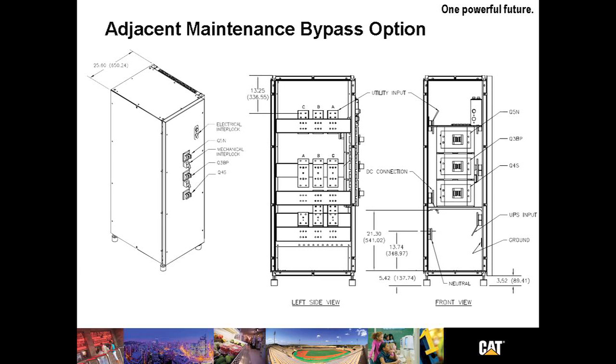The adjacent maintenance bypass option provides a three circuit breaker option for external wraparound and bypass for the system. Electronic interlocks are used in combination with Kirk keys. The matching cabinet is 26 inches wide. A remote version of this is available as well through special order.